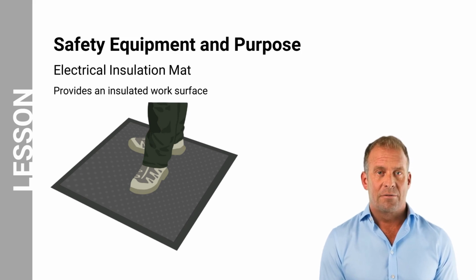Electric insulation mats are designed to provide technicians with an insulated work surface. They are made of non-conductive materials such as rubber, vinyl, or silicone. For BEV technicians, they are typically made of durable rubber or polyvinyl chloride, abbreviated as PVC material. They are designed to withstand high voltages and currents, and they are also resistant to oil, grease, and other chemicals. It is important to select a mat rated for the voltage and current levels of the electrical work that will be performed, and choosing a mat that is the correct size and shape for the work area is also essential.